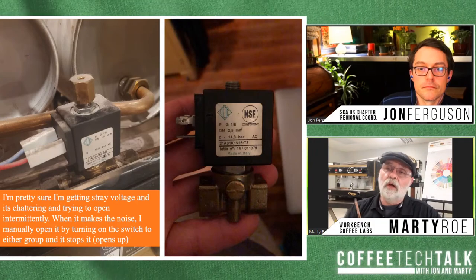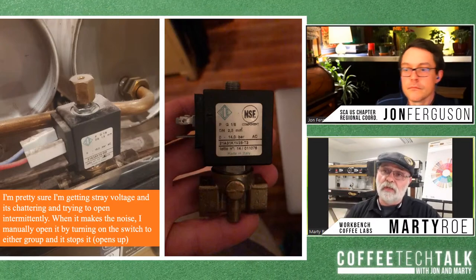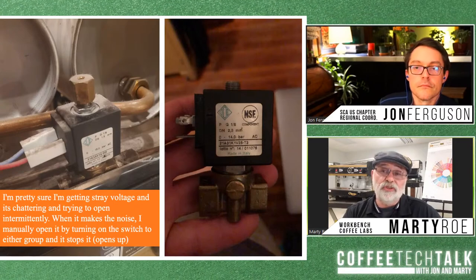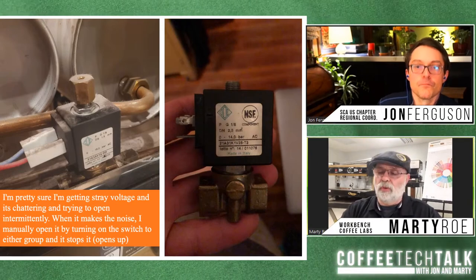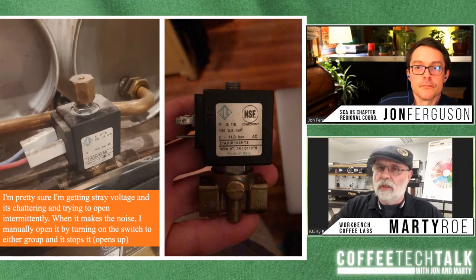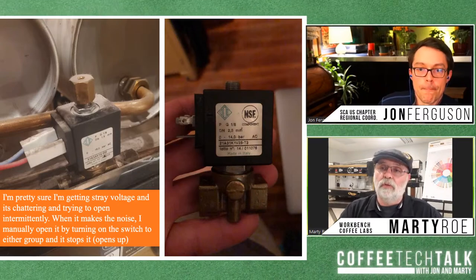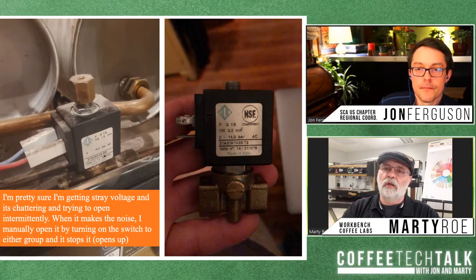And so what you'll find almost 100% of the time when we see these, that coil is rated from 220 to 240 or 220 to 230. And if you actually test the voltage on the wall, if your building is three phase, you're getting 208, give or take a little bit. So you're below voltage. So the magnet that you're creating with the electromagnetic coil isn't as strong as it is designed to be, because you're not feeding it the power it was designed to be fed. So the quick fix is to order a 200 to 208 volt coil and replace just the coil, and that should correct it.